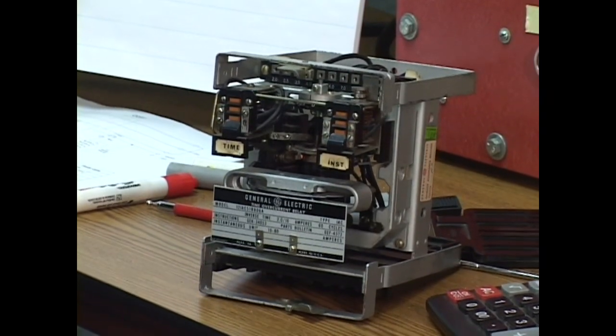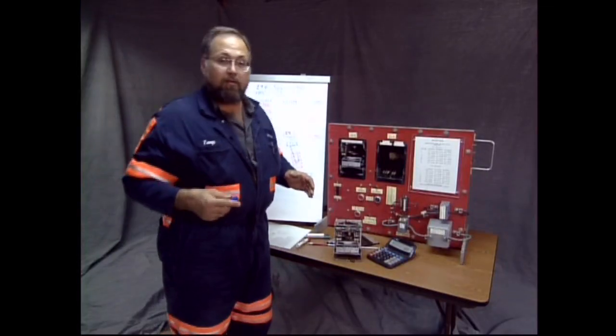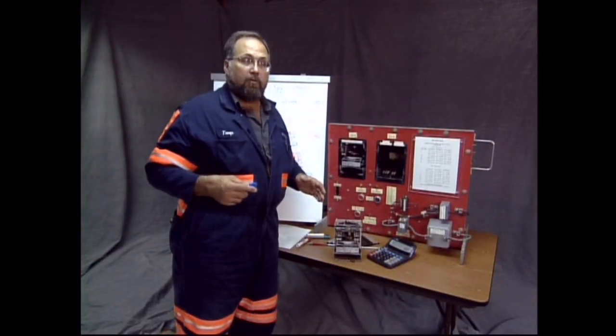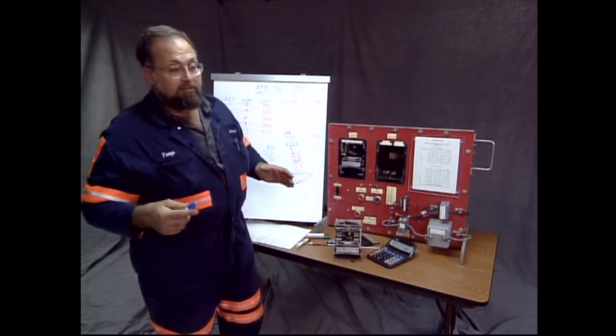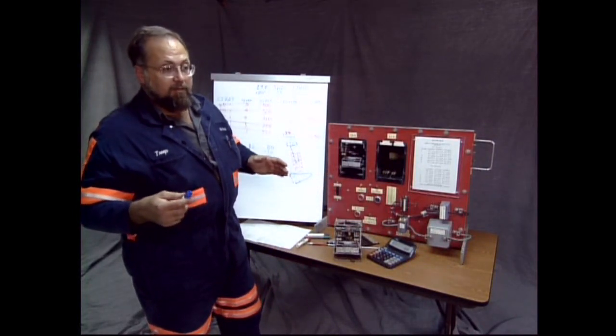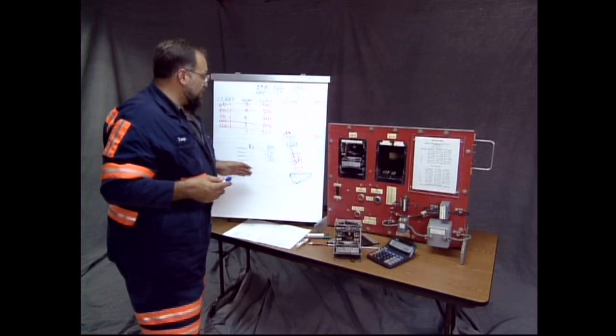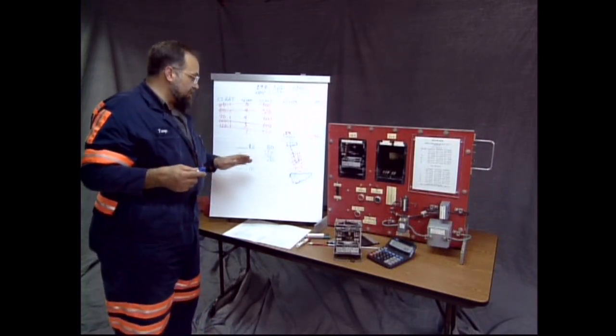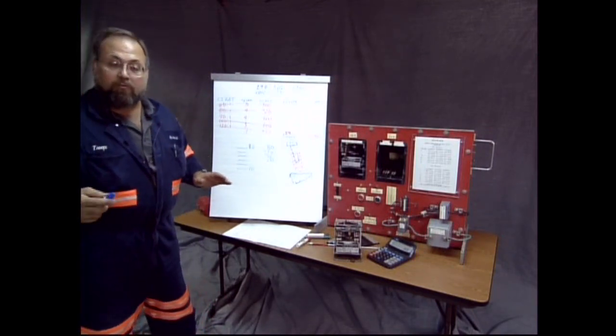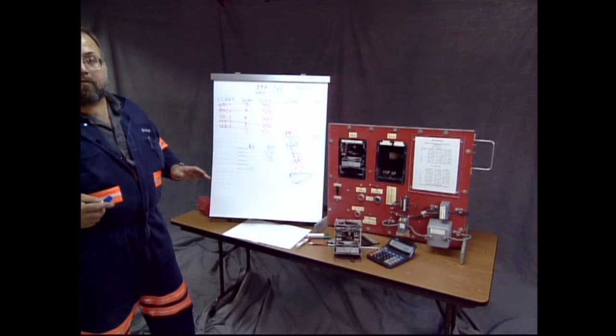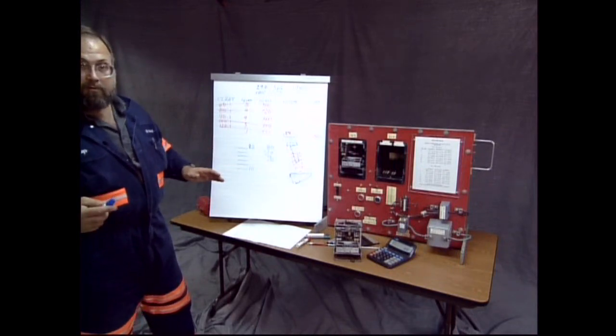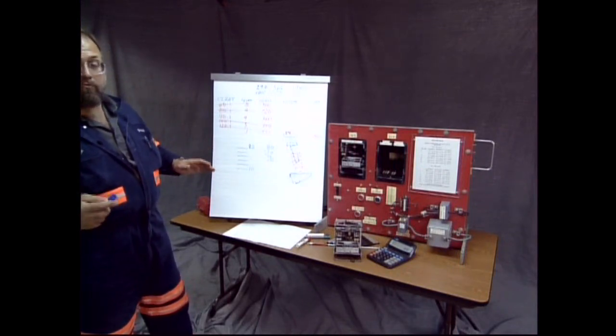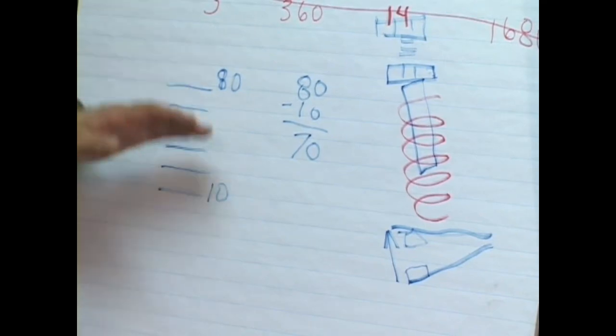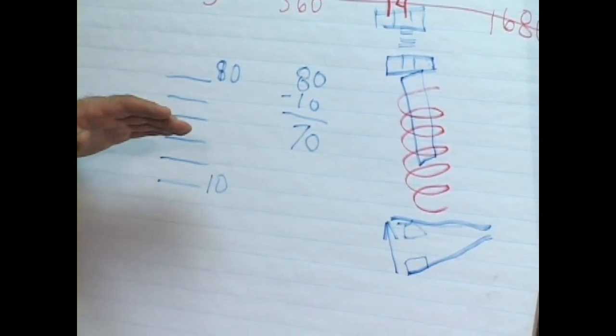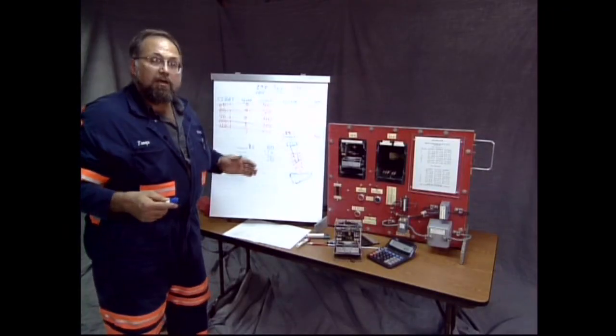and then adjust the relay for a pickup. Now there are several companies about that can adjust these relays for you. In the field, you may not always have that available to you, and you're going to have to make a field expedient adjustment. It's not going to be exactly accurate, but you can be in the neighborhood. And if you err, make sure that you err on the side of the angels and set it at a lower level. Because, like I said, this is fire insurance.